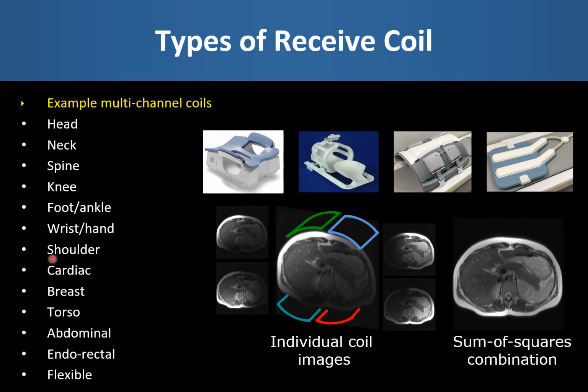There are a wide variety of different receiver coils with different numbers of channels. Here is a list of potential coils that you could purchase from your MRI vendor. Here, for example, is an 8-channel breast coil, an 8-channel brain coil, a 12-channel abdominal coil, and here a 32-channel cardiac coil. As already mentioned, each coil element is connected to its own receiver system, so images are reconstructed from each coil individually. So here on this simple schematic of a 4-coil element, we can see the individual coils, and then these images are combined to produce the final image. So we can note that the individual coil images have a spatial sensitivity that falls off with distance. However, this is somewhat compensated by the reconstruction or the combination of the coil images.